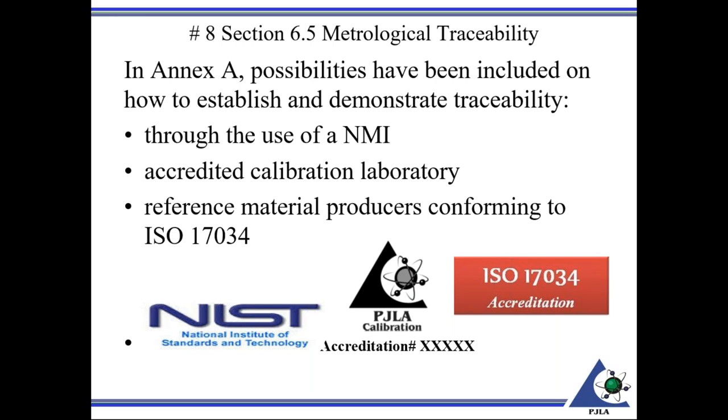or reference material. So in a nutshell, I call these slam dunks. If you go through the use of an NMI, National Metrology Institute, in the U.S. that is the National Institute of Standards and Technology, or you can go to another laboratory that is accredited in order to assure traceability, you're getting their traceable documentation, and you're getting something that they're accredited to perform, such as one of our PJLA accredited calibration labs, who should not be accredited if they were not providing traceable measurements.